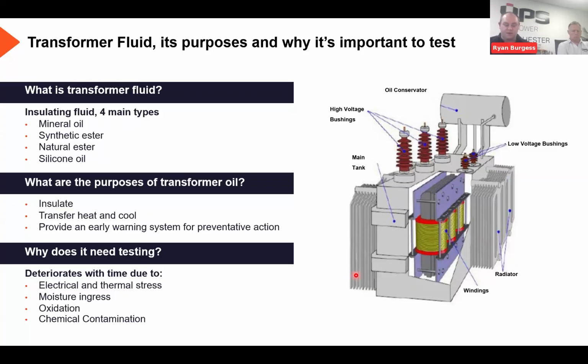So let's look at the purpose of the oil. First and foremost, a transformer oil is an insulator. So what do I mean by that? As an insulator, they control the flow of the electricity, preventing the current from jumping between winding to winding or from the core to the winding, which ultimately can cause short circuits, leading to reduced life of the transformer. Then it acts as a coolant. As a coolant, it carries the heat away from the core to the exterior of the transformer. This is done usually via convection currents, but in larger transformers, pumps can also be used to pump the heat away in the oil from the core to the exterior. This in turn allows for safer operation of the asset and a prolonged life of the asset.